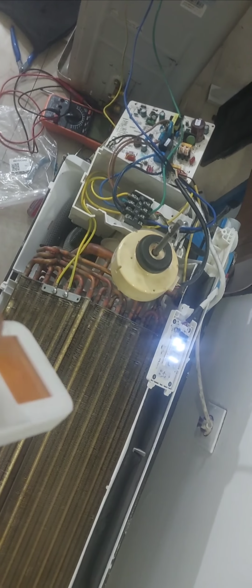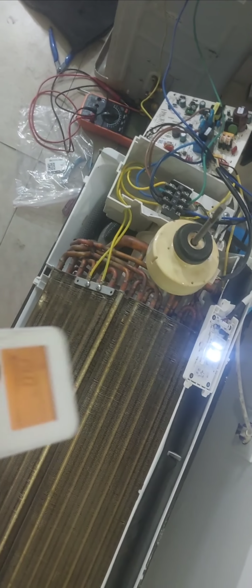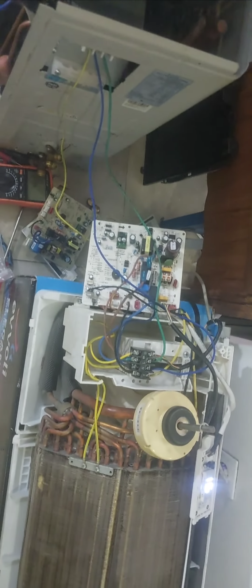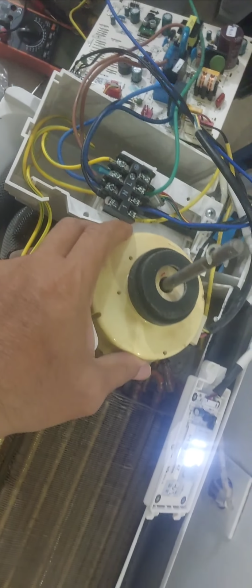Voiceover script 333. Today, we received an inverter air conditioner from a customer, who reported that the compressor was not starting and the outdoor condenser fan was not running. Upon initial inspection, we discovered that the system was showing error code E0. This fault usually indicates a communication problem between the indoor and outdoor units.